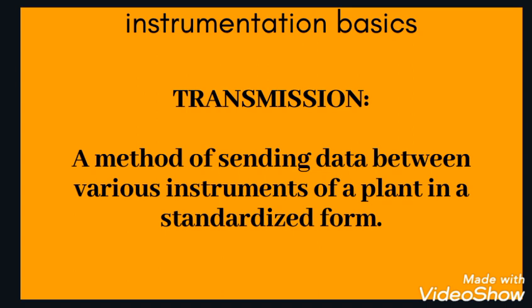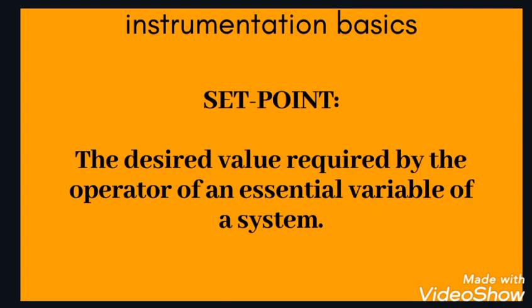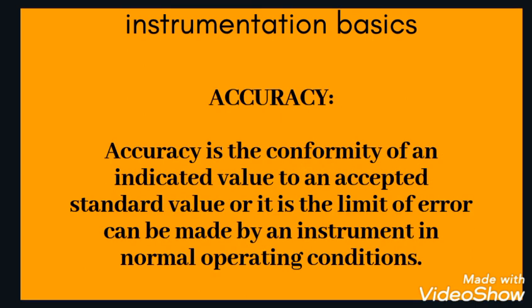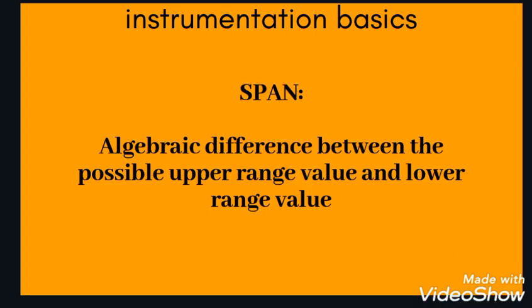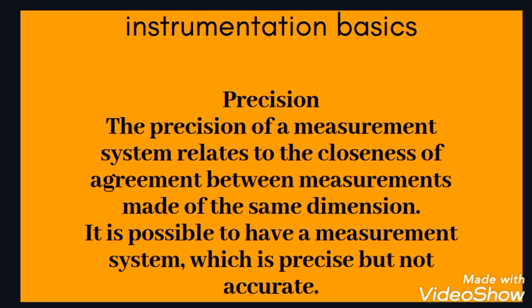Controller: a device in a control loop which regulates the error signals to zero, or a device which regulates the behavior of other devices or process variables to control the process. Transmission: a method of sending data between various instruments of a plant in a standardized form like 4-20 mA, 0-5 V, or 1-5 V. Setpoint: the desired value required by the operator of an essential variable of a system — where the operator wants the process variable (PV) to be. Accuracy: the conformity of an indicated value to an accepted standard value, or the limit of error that can be made by an instrument in normal operating conditions. Span: the algebraic difference between the upper range value and the lower range value is called the span. For example, if the range is 0-100, then the span is 100.